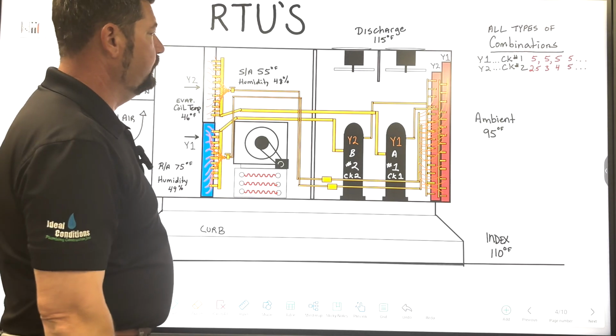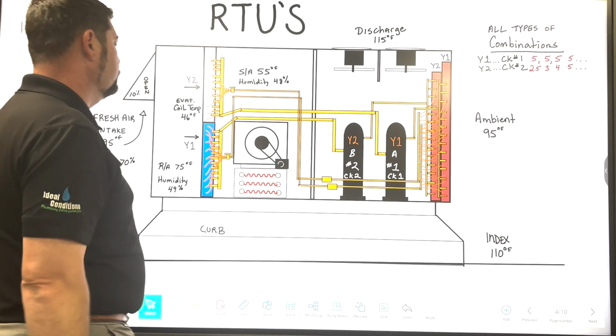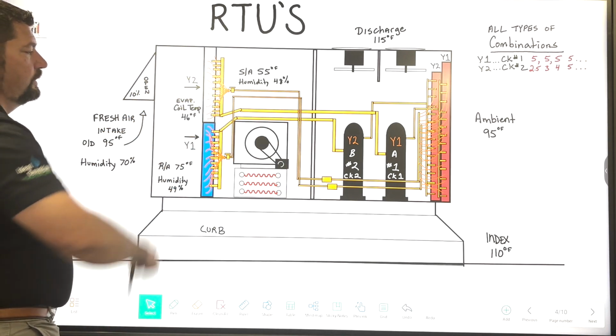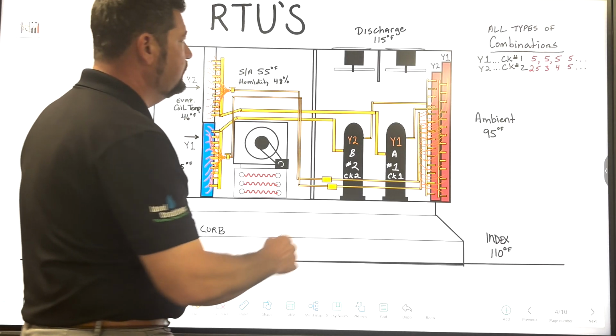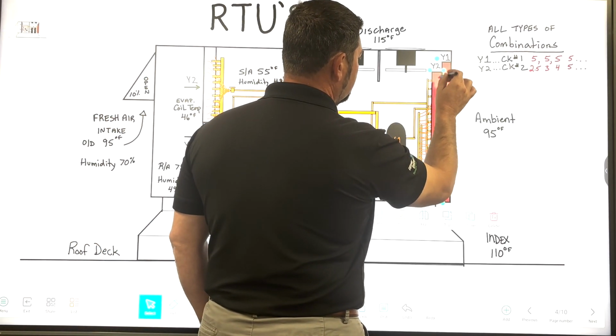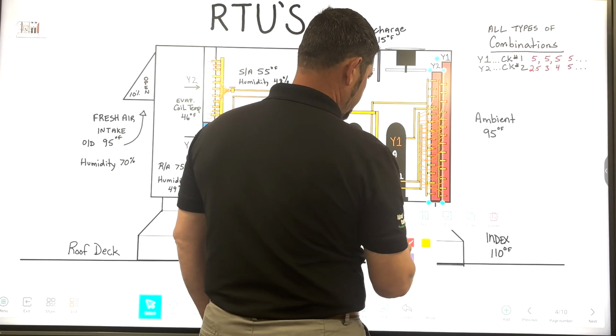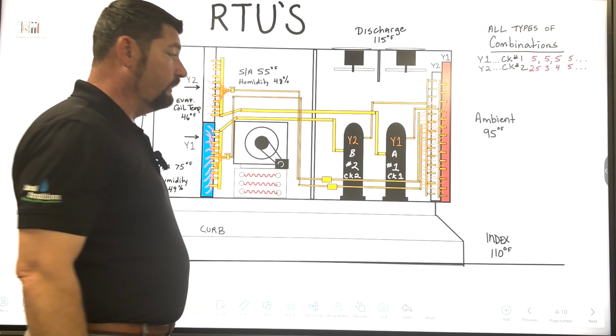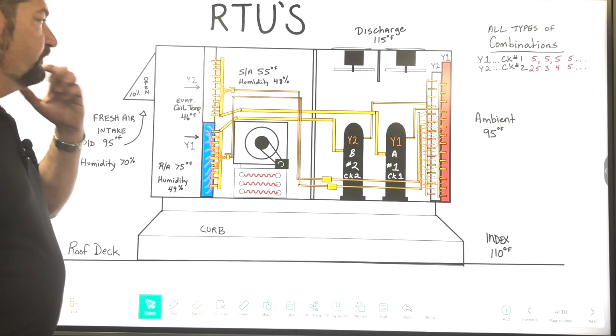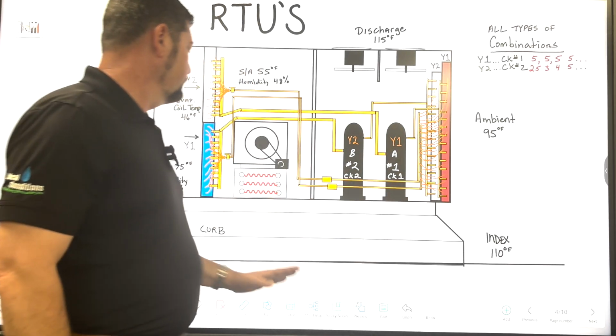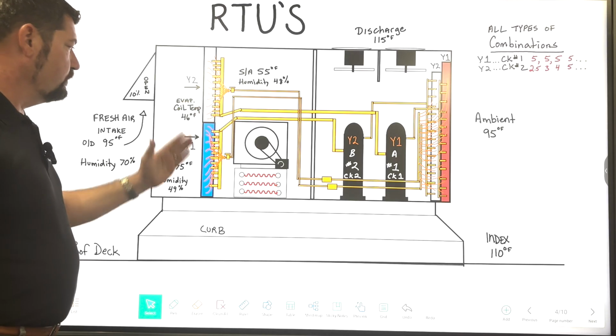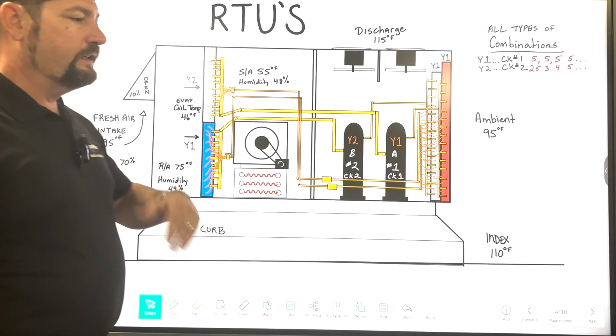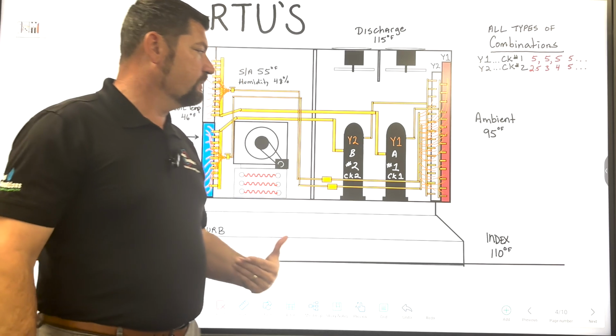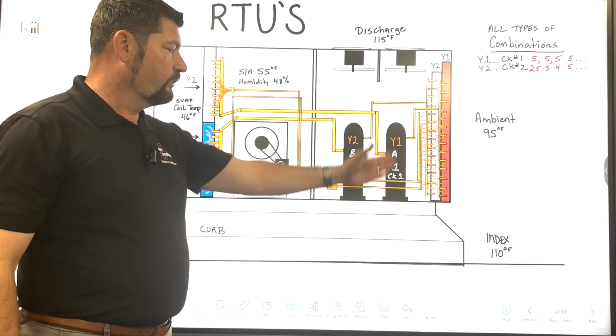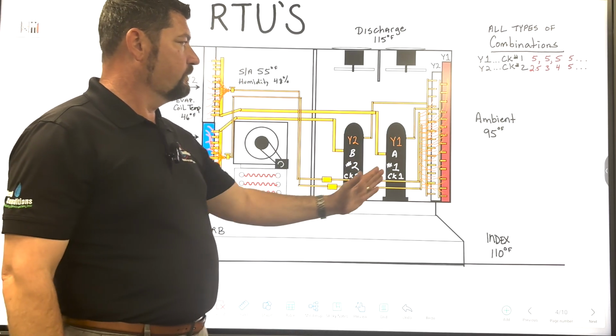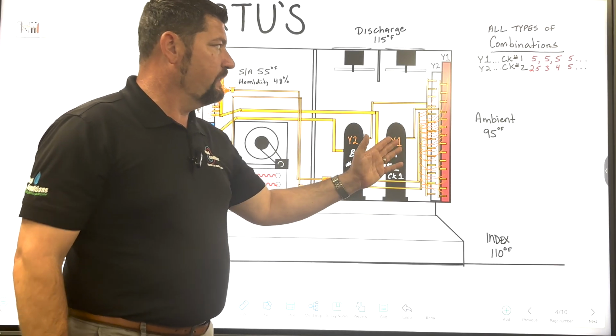Away some of that capillary tube so I can get my pin on that square. And so if the Y2 staged down, I'm going to go ahead and take Y2 over here. This just represents that either it's out of gas or the compressor's just off. So we're only running circuit 1, Y1, right, and Y1 over here. When you only have a low demand and you're trying to just maintain the temperature in the building, you only need the first circuit to be running. So we're running one circuit, which it can be in any combination.